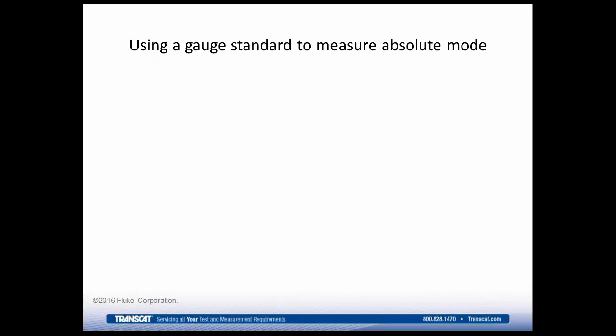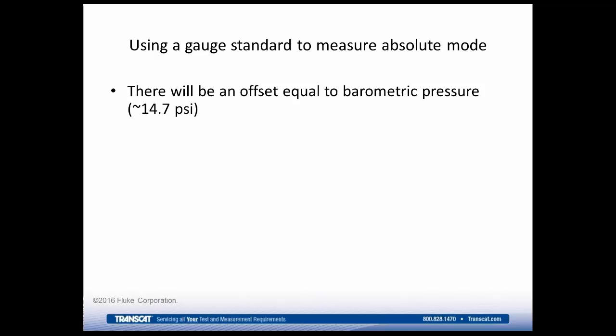Let's look first at a situation where you need to calibrate an absolute mode device, but all you have is a gauge standard. The first thing you need to consider is that there will be an offset equal to barometric pressure. So if you have an absolute device under test and a gauge mode standard sitting next to each other, with everything opened up to atmosphere, one of them will be reading about 14.7 psi and the other one will be reading 0.